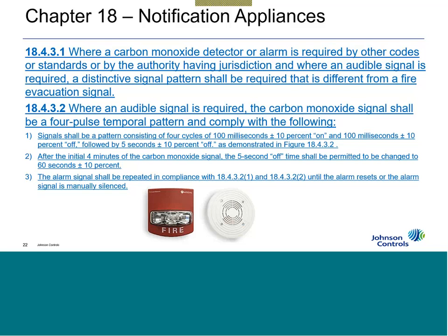Code now says temporal 3 is to be used to indicate not to be where you are. Meaning if I hear temporal 3, I need to relocate, go to another floor, or possibly evacuate, depending upon the response plan for that building. But it doesn't mean anymore that I have to evacuate. So now we have temporal 4 come along for carbon monoxide. The Carbon Monoxide Committee in NFPA 720 back in the early 2000s said, we need a different signal.